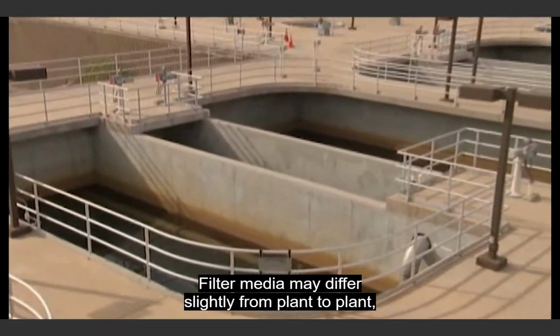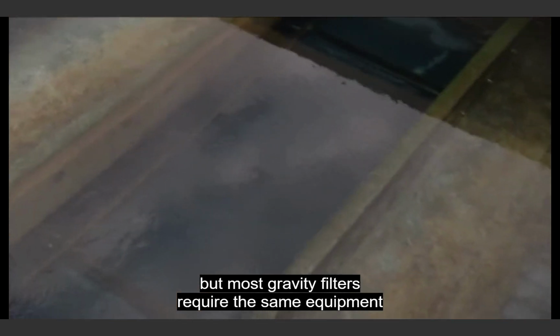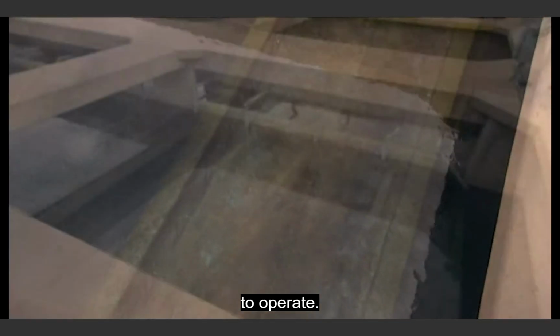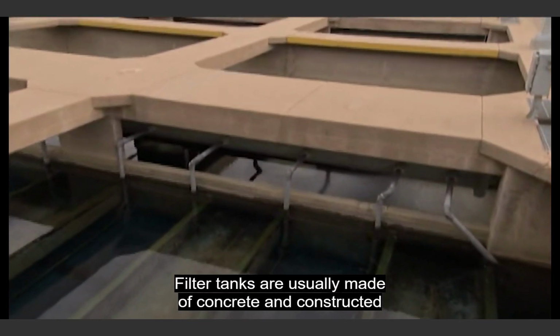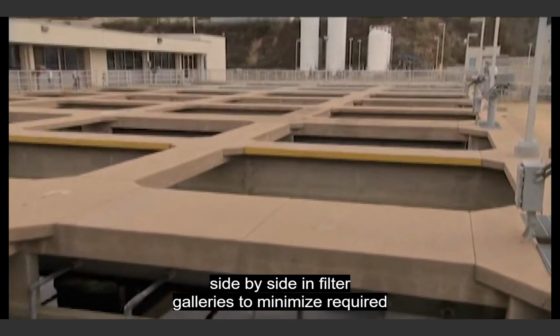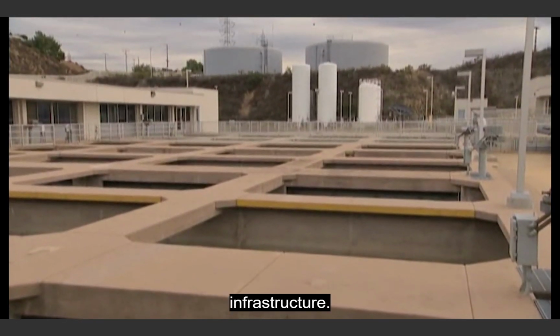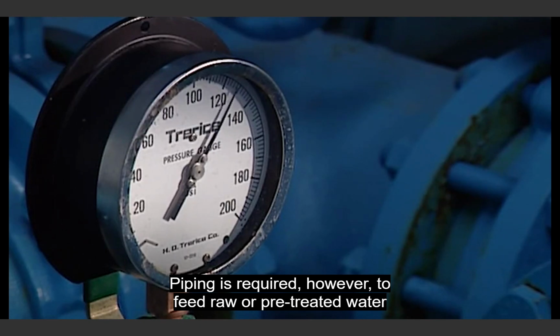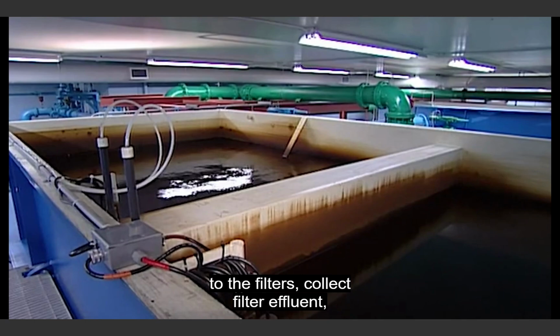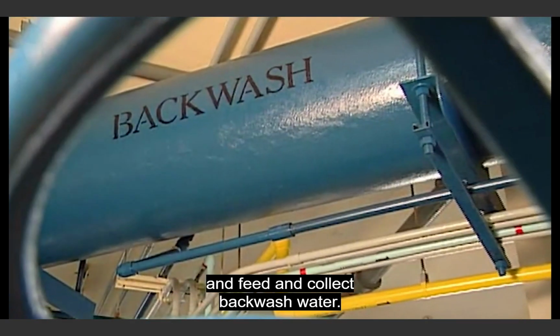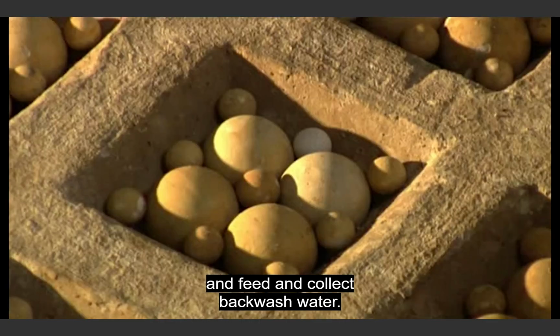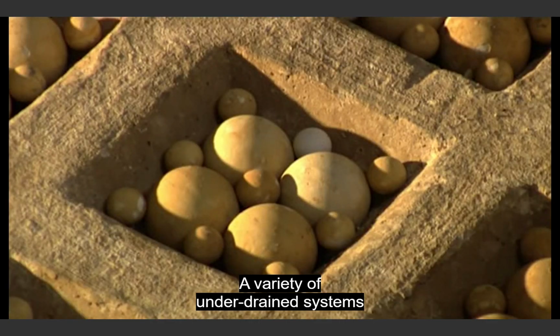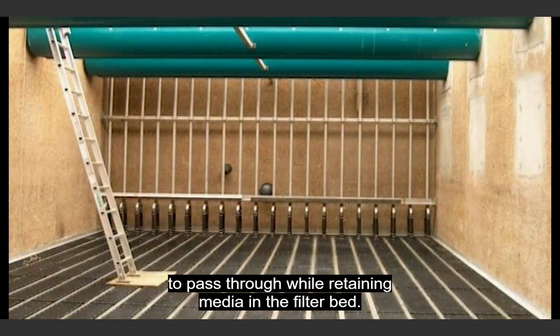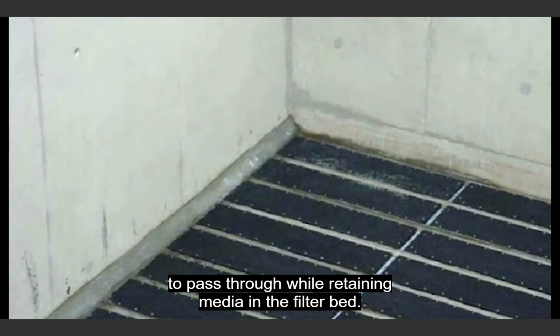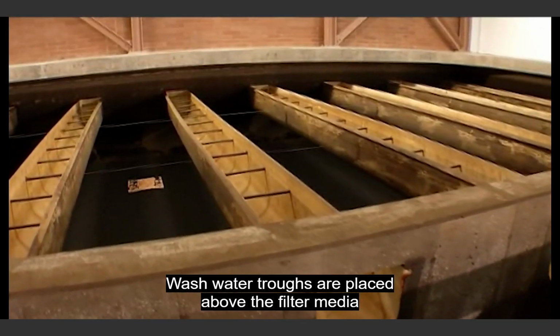Filter media may differ slightly from plant to plant, but most gravity filters require the same equipment to operate. Filter tanks are usually made of concrete and constructed side by side in filter galleries to minimize required infrastructure. Piping is required, however, to feed raw or pre-treated water to the filters, collect filter effluent, and feed and collect backwash water. A variety of under-drain systems are available to allow filtered water to pass through while retaining media in the filter bed. Wash water troughs are placed above the filter media to collect backwash water and carry it to waste.